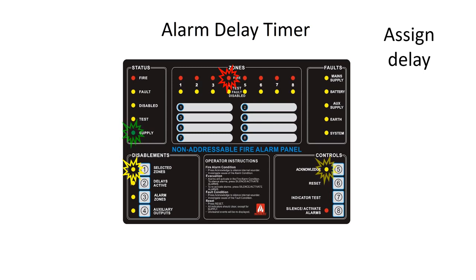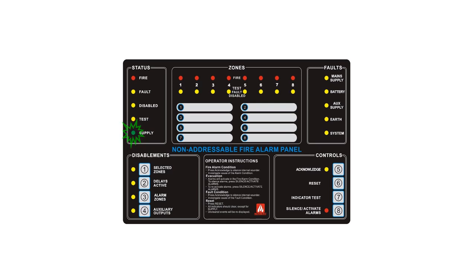If the delay is required to be assigned to other detection zones, repeat the process for the additional zones. When the delays have been assigned to all the detection zones, press the Selected Zones button to exit. The panel will remain in access level 3.